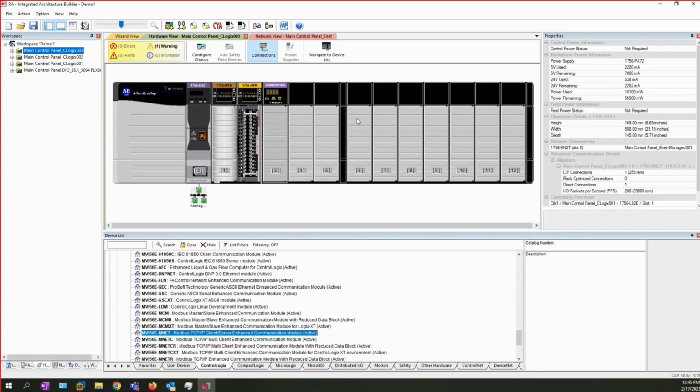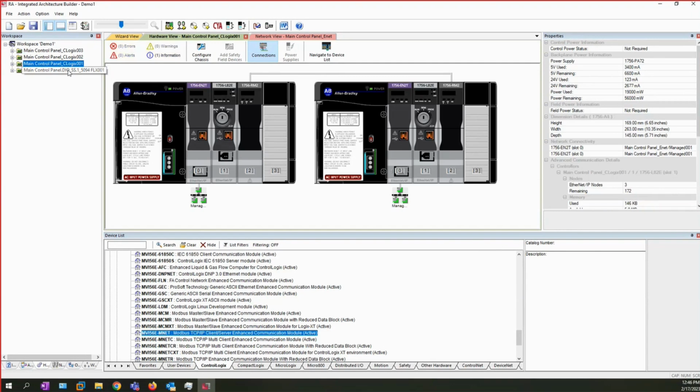And as you'll notice, as I've added things here, it's going to make adjustments over on the right side, as far as your power consumption and so on. So it's constantly taking that into account: how much power am I drawing off of this particular power supply? Is it going to flag it if I exceed the capacity of this power supply and recommend a bigger one? Yes, it will. You're going to see something in red telling you that you've overloaded this power supply.